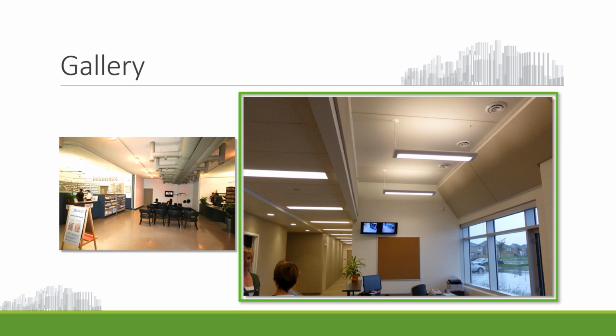While keeping indoor comfort conditions right using just outside fresh air, the picture to the right shows the effects integrated ventilation design can have on the perimeter of the building. Notice there's no ducting on the right-hand side above these windows, and the ceiling can be allowed to be higher. In a work situation, the higher the better the space is for productivity—it just makes a nicer, more comfortable space.